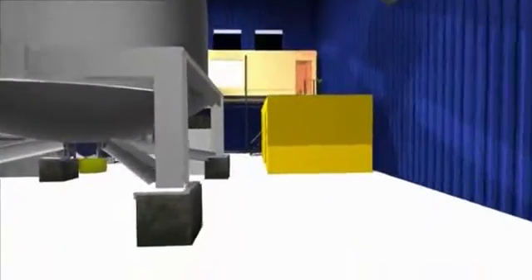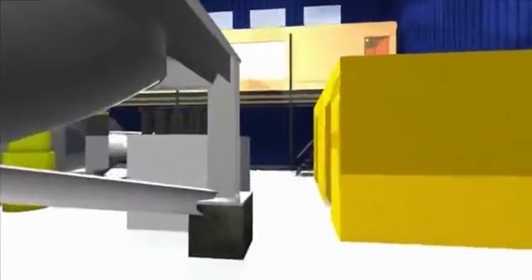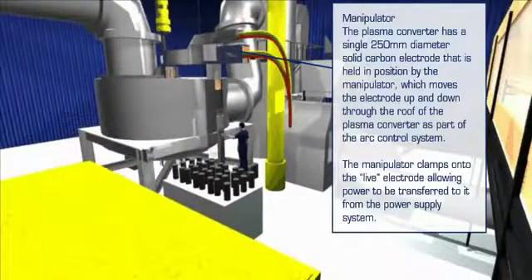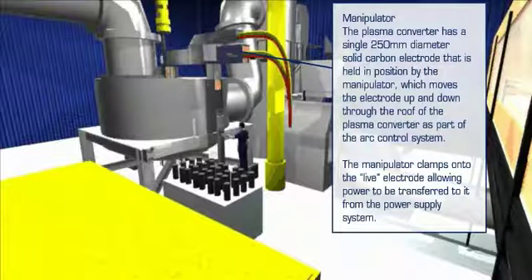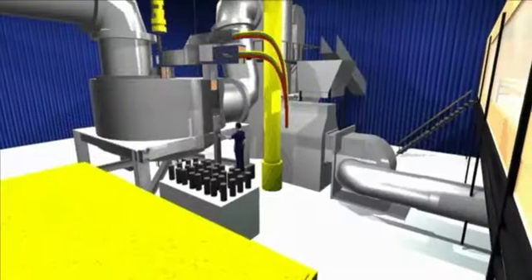We're now going round the back of the plasma converter to view the electrode manipulation area. The plasma converter has a single 250 mm diameter solid carbon electrode held in position by the manipulator, which moves the electrode up and down through the roof of the plasma converter as part of the arc control system. The manipulator clamps onto the live electrode allowing power to be transferred to it from the power supply system. As the system operates as a continuous 24-hour, 7-day process, additional electrodes need to be attached without interruption. An electrode jointer is used to screw 1 metre long new electrodes onto the live electrode while the system remains in operation.